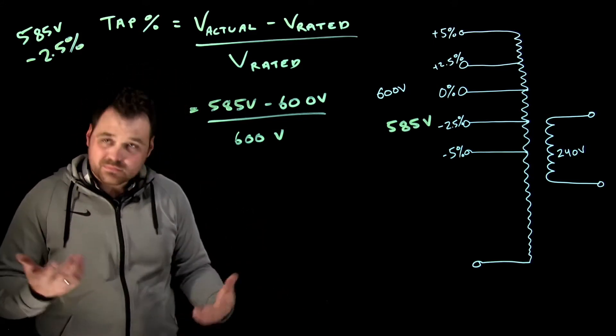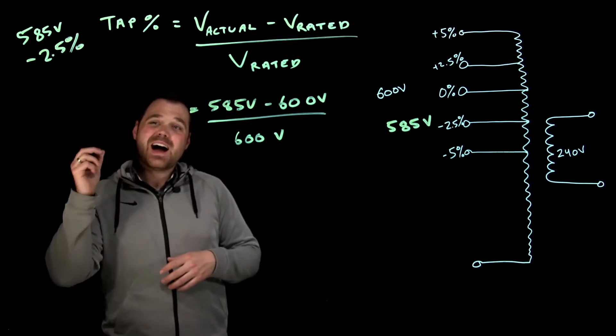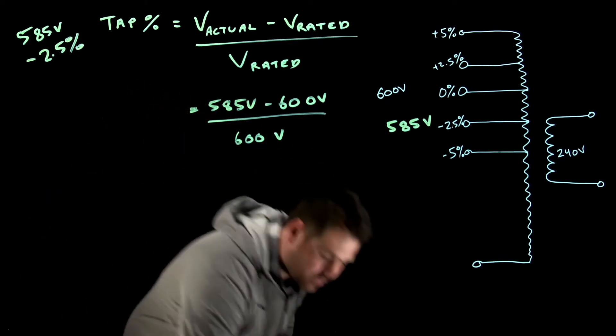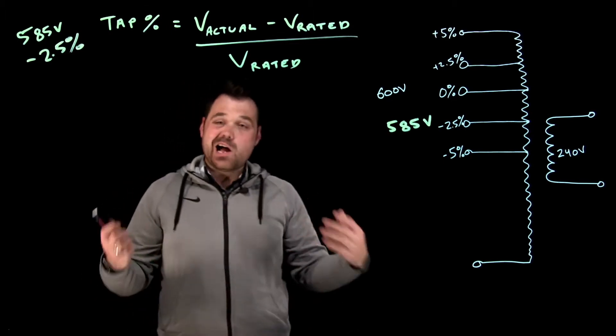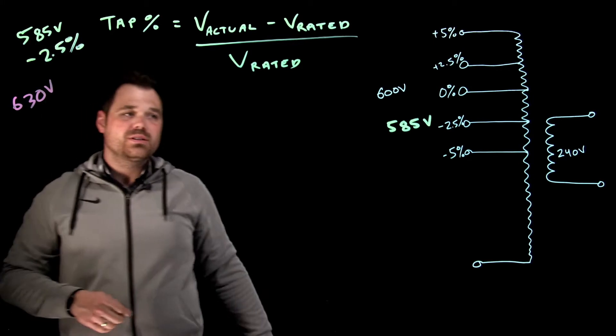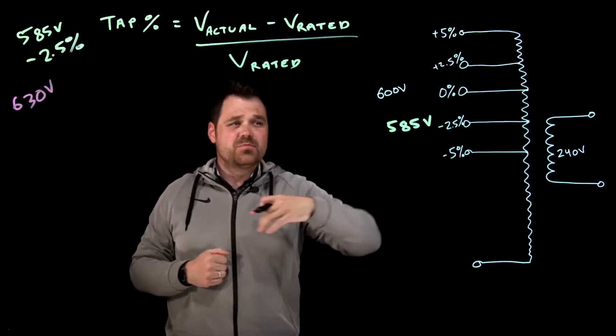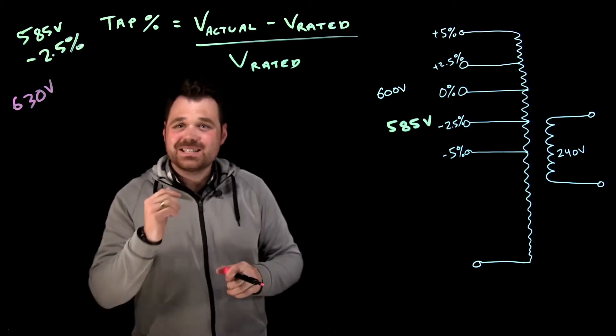So, well, that's great. That's all fine and dandy. But what if I had higher than rated voltage? Let's see if that formula works for that too. All right, so now we've got higher than rated voltage. Now let's say, oh man, we got 630 volts. We're close to the distribution transformer. We got 630 volts. Let's see if we can apply the same formula.